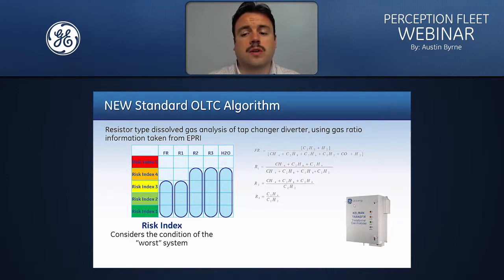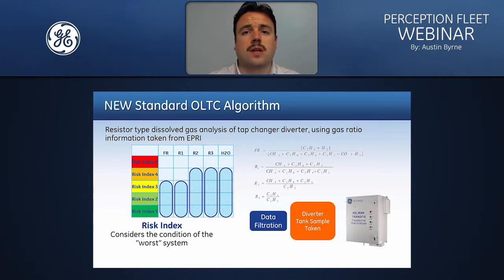So whenever the diverter tank is sampled, again, we filter the data to take out any spurious results, and then we perform a calculation based on the ratio information taken from EPRI. A risk index is then applied for each of the ratios, and we then take the worst risk index of the ratios, and that is the categorization that's applied for that asset. So you can see we have a risk index of 4 for this particular algorithm.